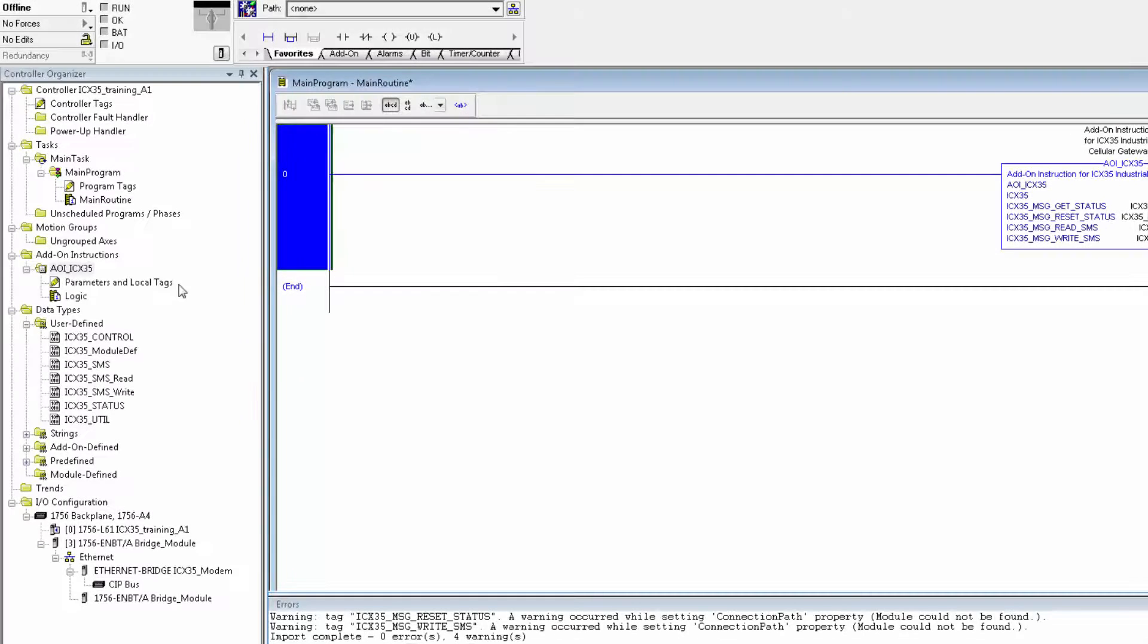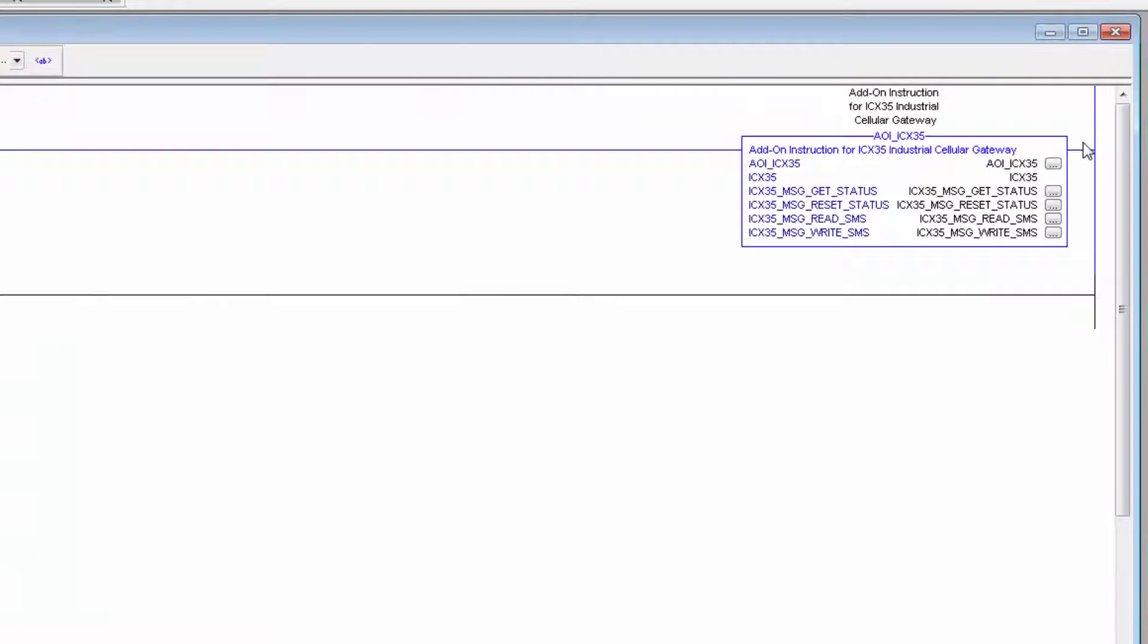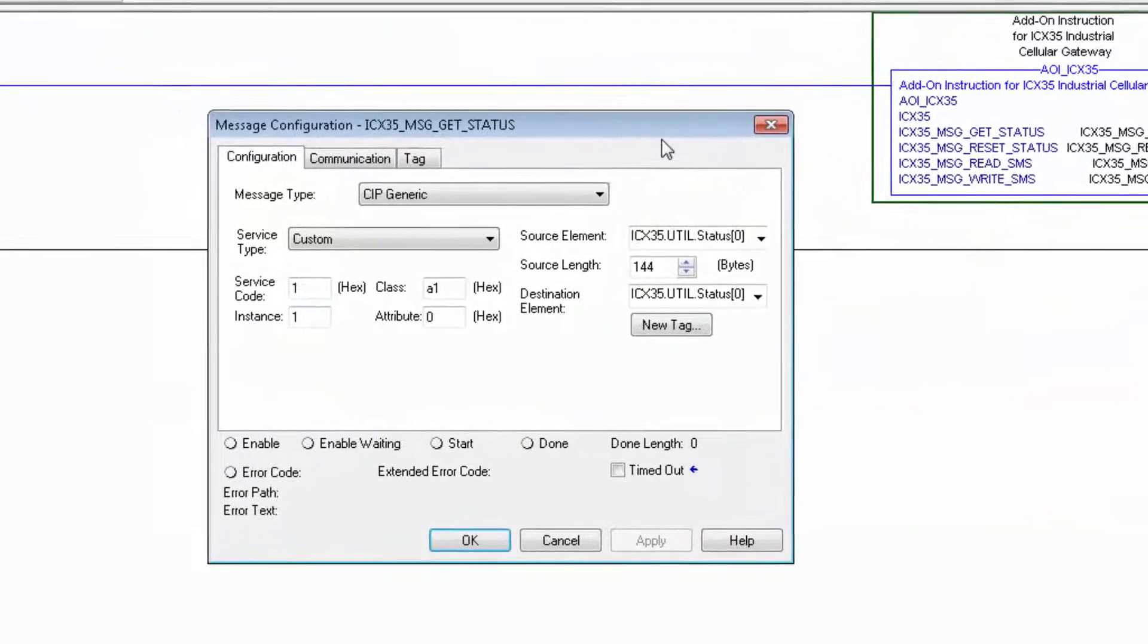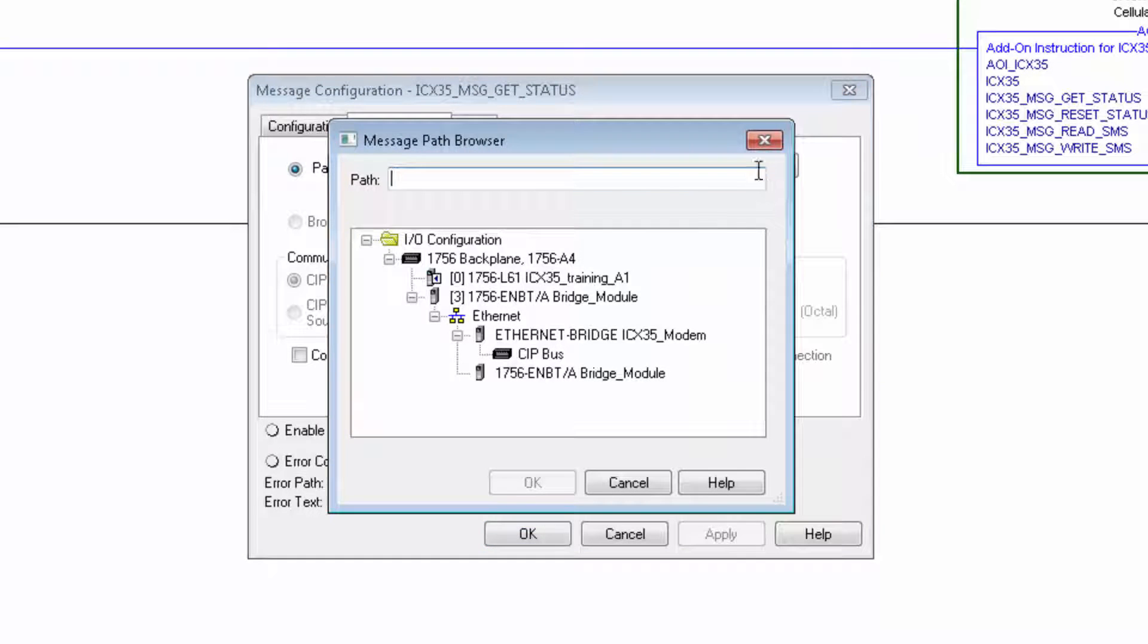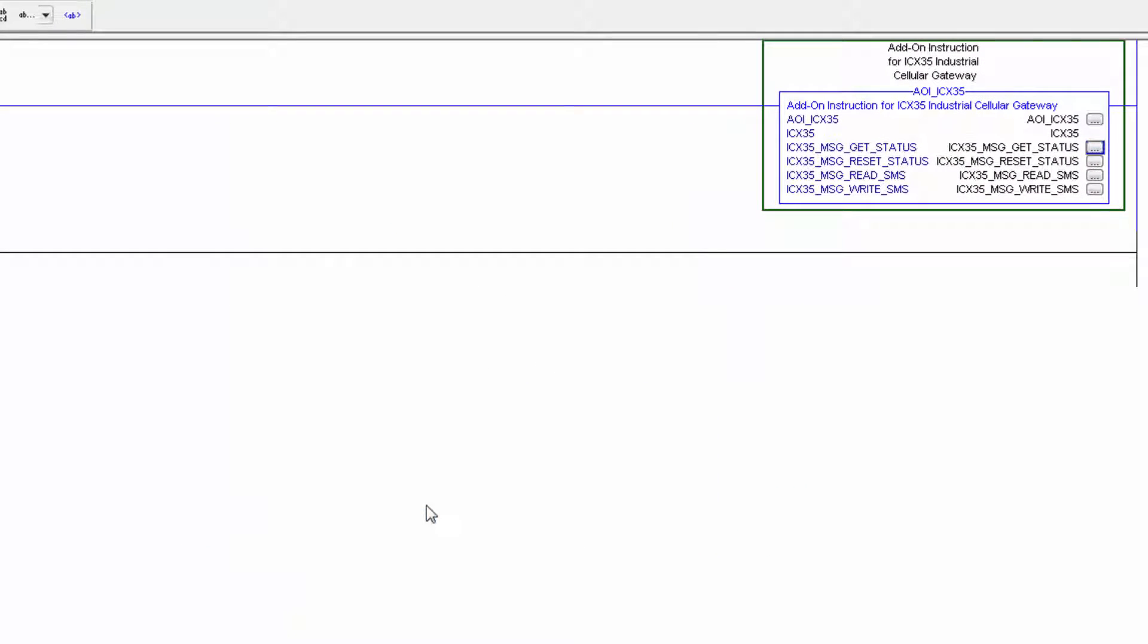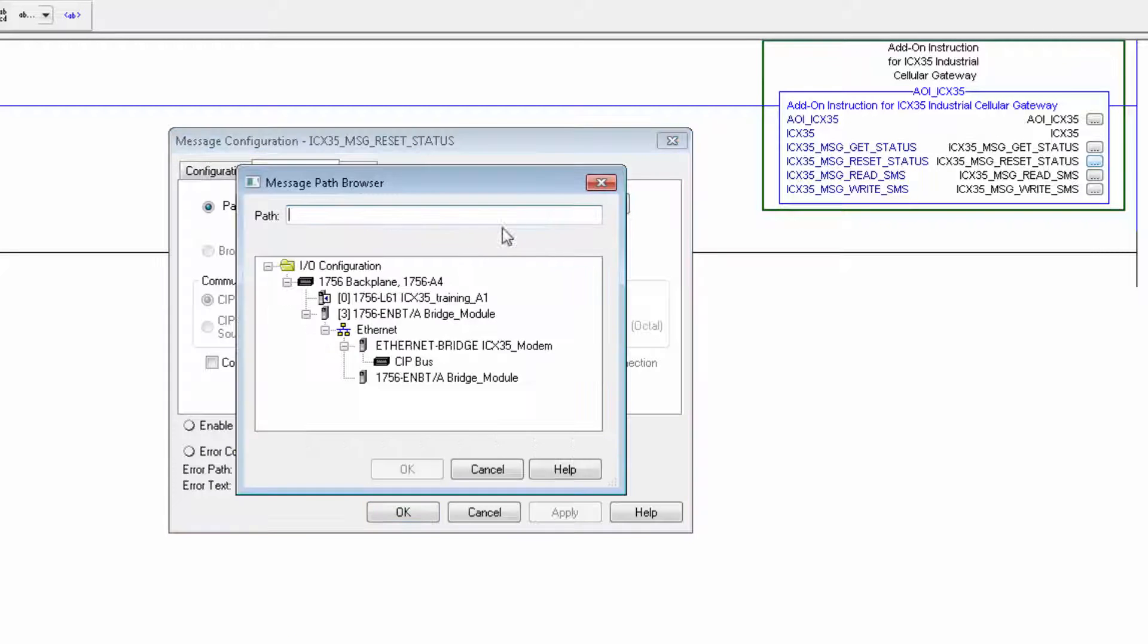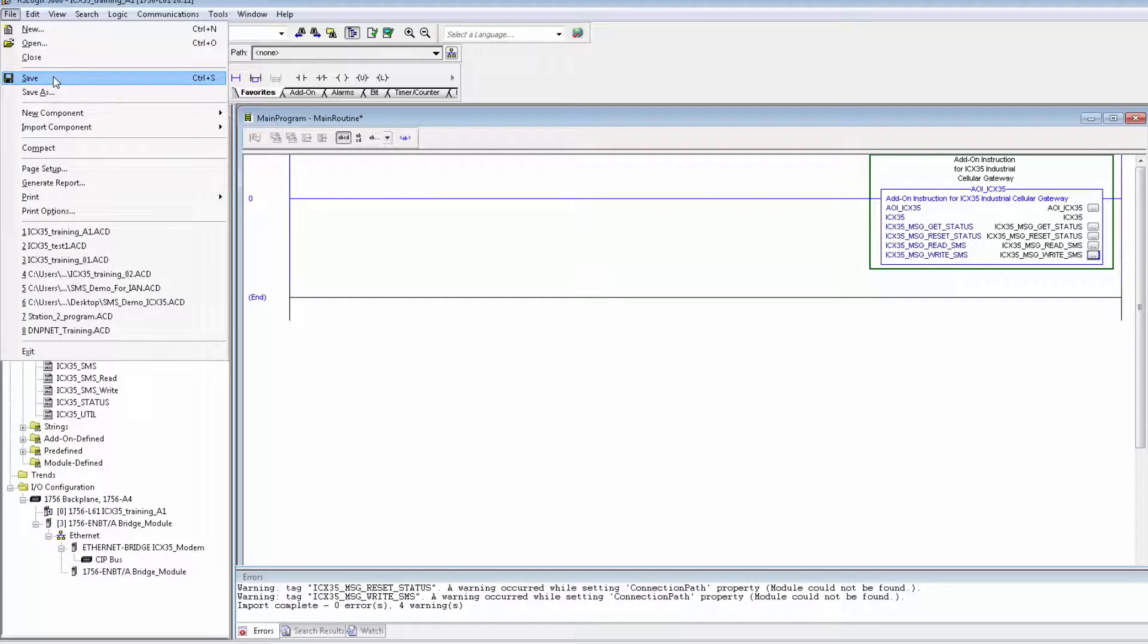If you do give the ICX35 a unique name, you'll need to reconfigure the path from the controller tags to your ICX35. To do this, you'll notice there are these five configuration dialog nodes. The top one you should just leave alone, but for each of the bottom four, which correspond to controller tags for the ICX35, you'll click on them. In the window that opens, you'll open the communication tab, and for the path, you will browse for and select your ICX35. Once selected, you can click OK, and you'll do this for each of the four nodes here. Again, this is only necessary if you gave the ICX35 a unique name other than ICX35. At this point, it's a good time to save your project.